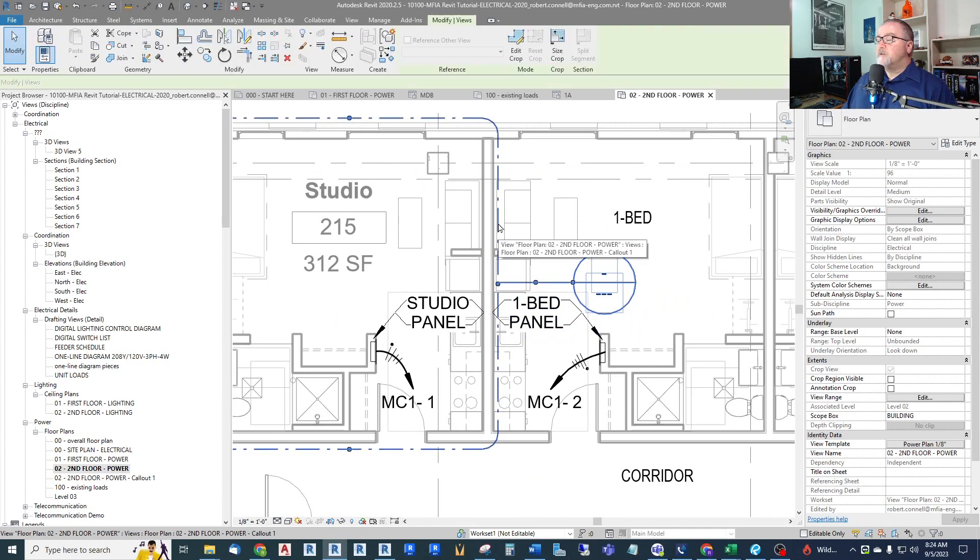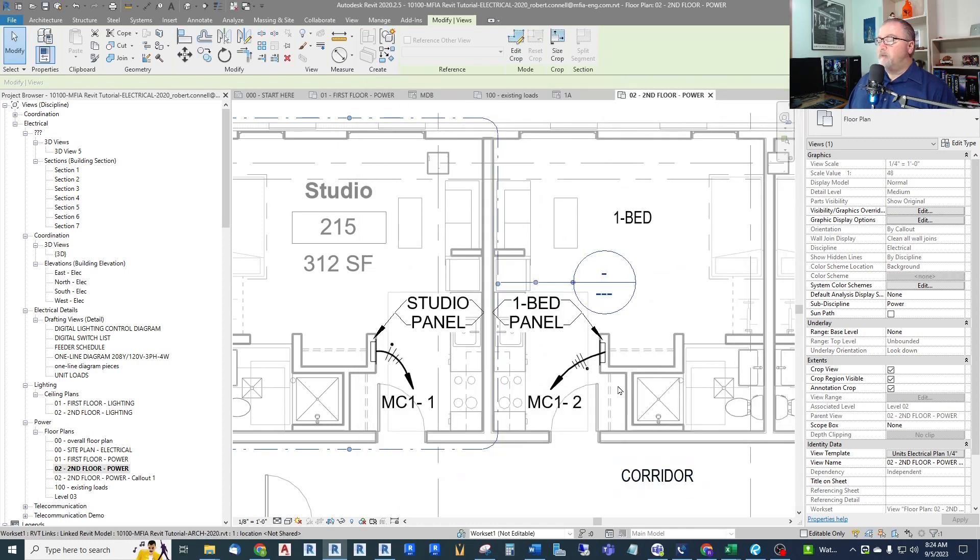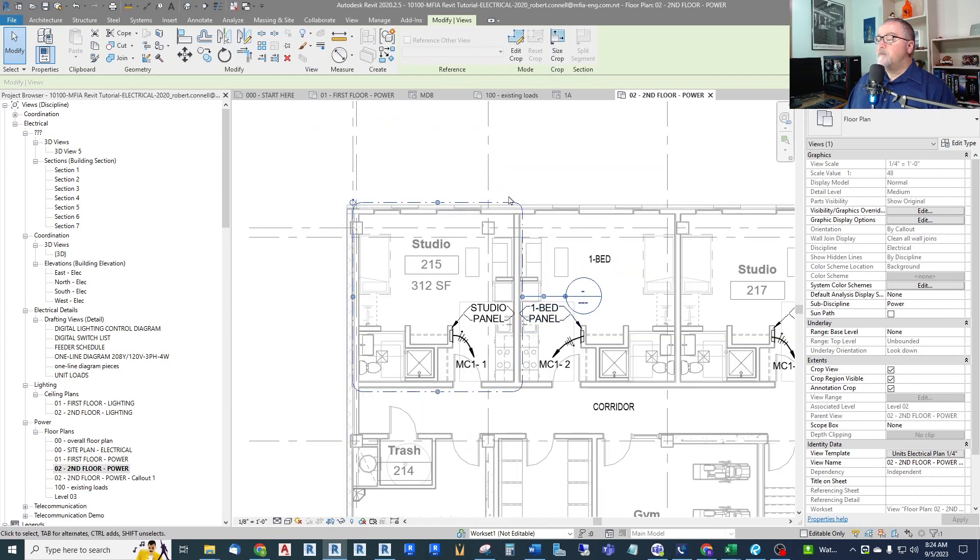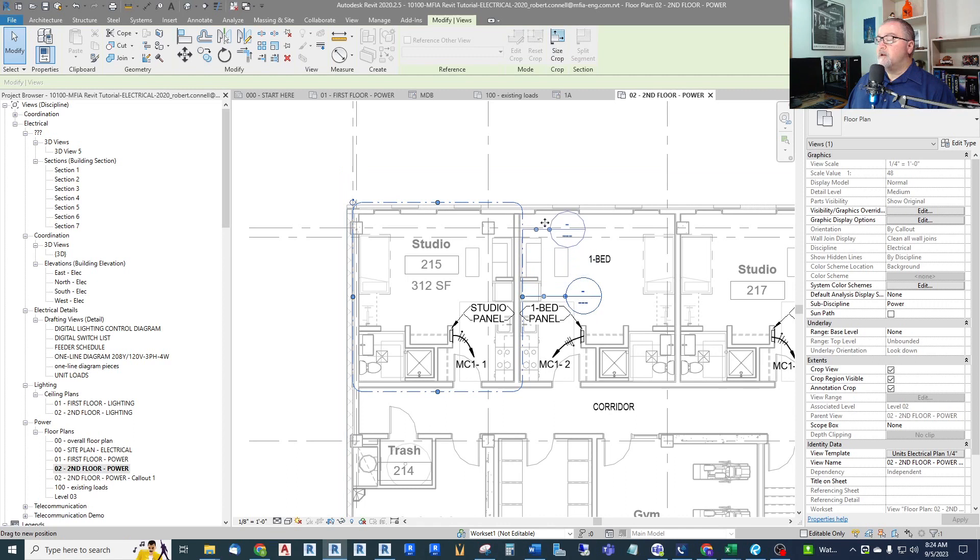So that is the callout. And then if you click on the actual callout itself, you're clicking on a view. We can down here pick the view template for this. What we do here is we already have it in here: units electrical plan. That means apartment units. We have a separate view template for units because we are going to be messing around with some worksets to turn things on and off. So I'm going to pick my units quarter inch and I'll show you what's special about that. Also, when I have this boundary selected, I can move the detail bubble to where I'd like.